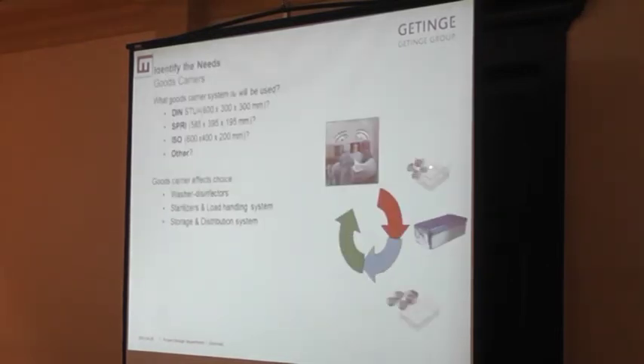And what kind of basket do we have - do we use baskets or containers? Do we use the DIN system, the SP system, the ISO system, or another? And what kind of containers - DIN containers or some other US-style container? This affects the depth of the sterilizers, to be optimized. Depending on the system, we choose a different depth of sterilizer, and even the washer depth can differ between DIN, SP, or ISO. This affects a lot, including the trolleys that go out to the OR, depending on whether they're made for containers, SP baskets, or DIN baskets.